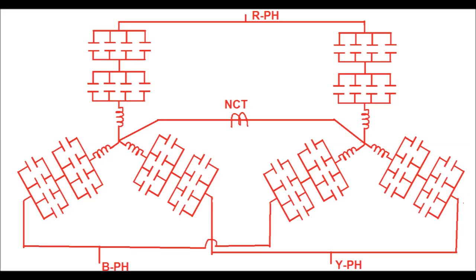The schematic diagram for the double star capacitor bank for 20 MVAR rating at 33 kV system voltage has been shown. In each phase of each star connection there exist eight capacitors, of which there are two series groups, and in each series group there are four capacitors connected in parallel. In each phase of each star connection there also exists a reactor, and between the neutral points of the two star connections there exists an NCT.